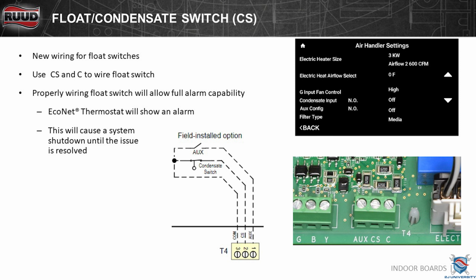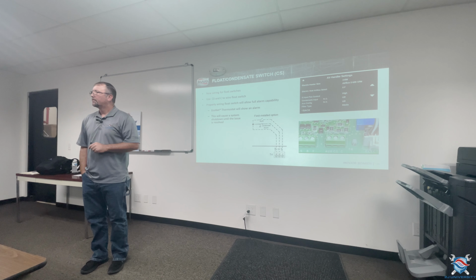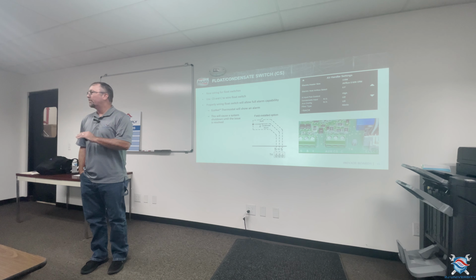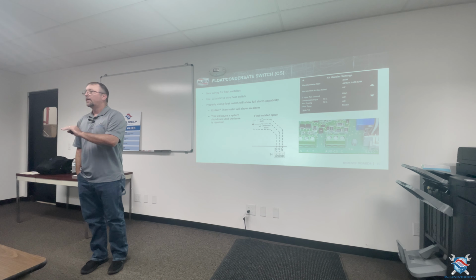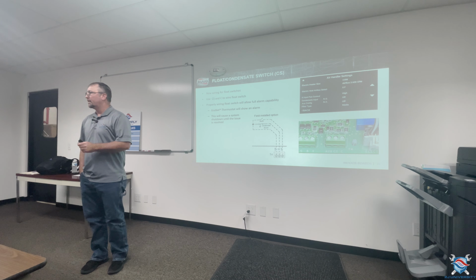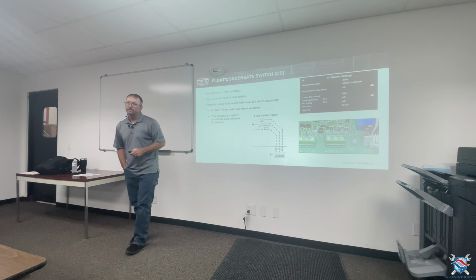So this is that wet switch I was talking about and how you connect it. You're just going to take the wet switch back through 2 and 3, and then anytime that condensate switch opens, you'll get that alarm. I was asking earlier, say I have an automatic... Correct, because they're all normally closed switches. If any one of those opens at any given time, it's going to open that circuit and then give it a flag. Yeah, absolutely.